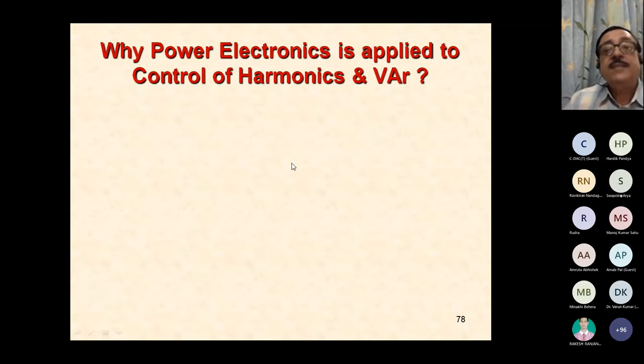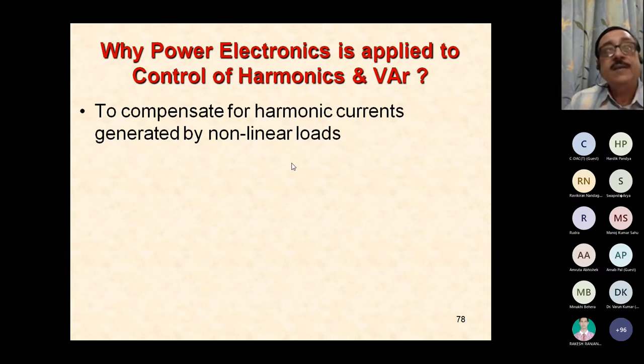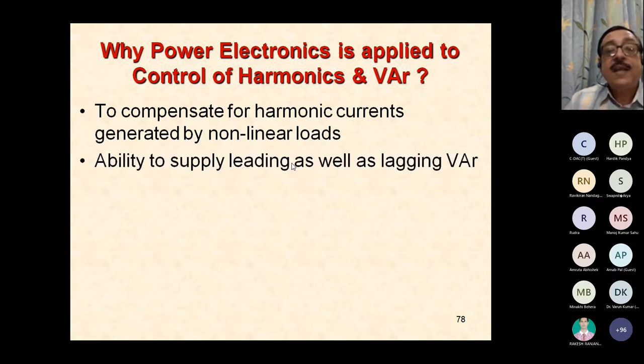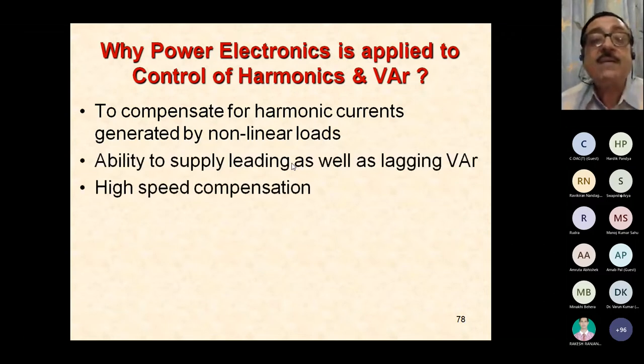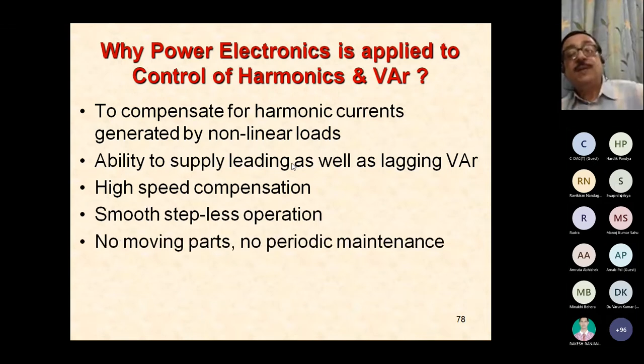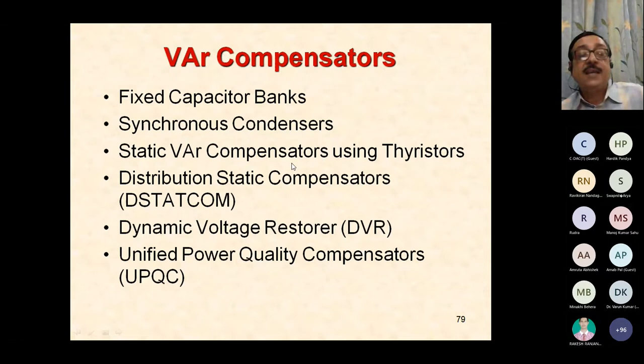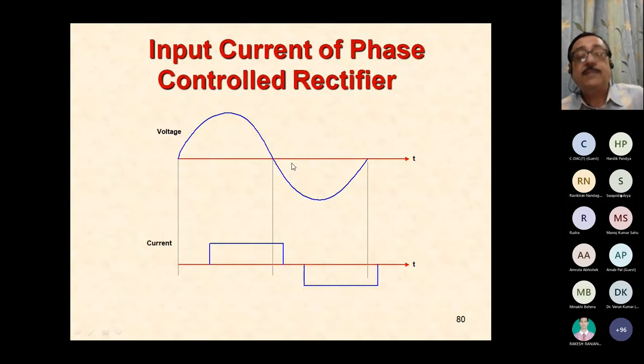Okay, why is power electronics now being applied to control of harmonics and VAR instead of passive systems? To compensate for harmonic currents generated by nonlinear loads, it has the ability to supply leading as well as lagging VAR. High speed compensation, smooth stepless operation, no moving parts, higher efficiency. And we have VAR compensators in the form of fixed capacitor banks, which is in today's power electronics activity becoming a bit risky. We have synchronous condensers, rotating machines, overexcited, which provide the amount of VAR required. And we have distribution static compensators or DSTATCOMs, which I'm going to talk about.